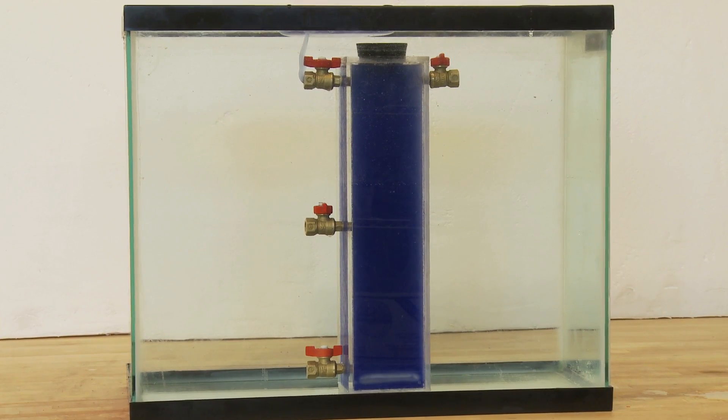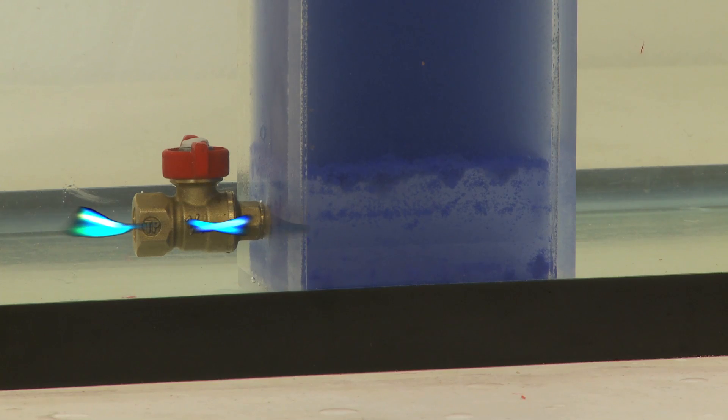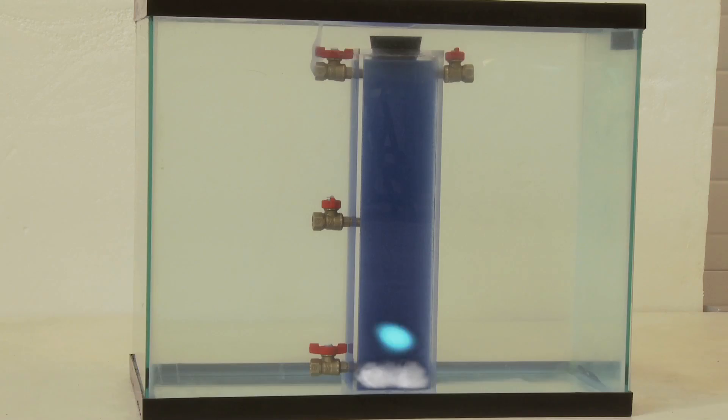Air is coming in down low, and it's leaking out the top. We can see here that there's some very cold, dense outdoor air that's come in through the crawl space, and it's settled in down at the bottom. As that air warms up, it heats, it rises, and gradually it works its way to the top. And you have this continuously ongoing cycle through stack effect where air is leaking out the top, coming in at the bottom, and you're paying for that, so you're losing some heat.